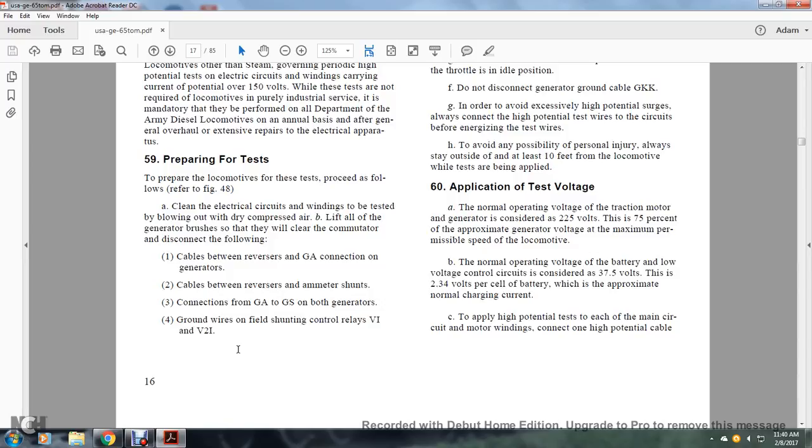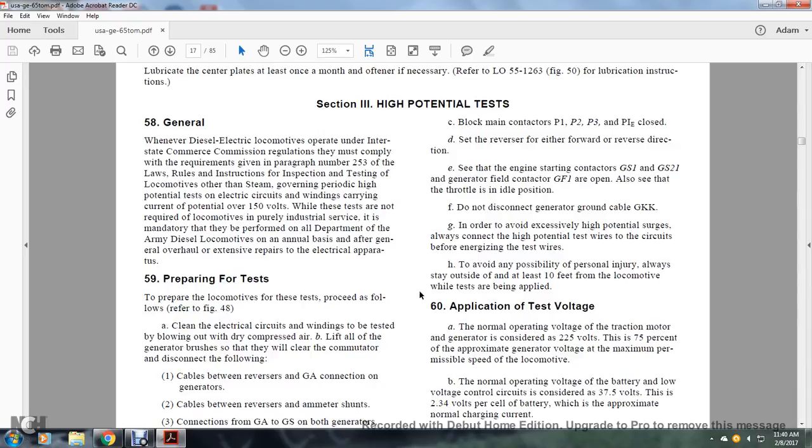Section 59, Preparing for the Test. Clean electrical circuits by blowing out with dry compressed air. Lift the generator brushes so they clear the commutator. Disconnect the following: cables between reversers and GA connection on the generators; the cable between the reverser and ammeter shunts; connections GA and GS on both generators; ground wires on the field shunting control relays V-1 and V-2.